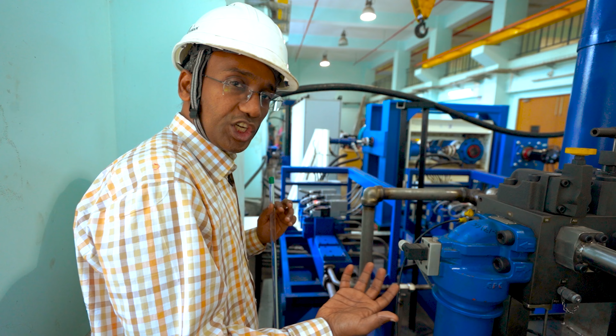Now when the system is running, the oil can become hot. So in order to cool the oil, we have a recirculation pump. From the recirculation pump, the oil goes into the heat exchanger. So this is a heat exchanger, a 25 kilowatt rated heat exchanger, and then from the heat exchanger it goes through 2 filters with different mesh sizes back into the tank. So the recirculation system is used to cool the oil and also to remove the metal debris from the system.